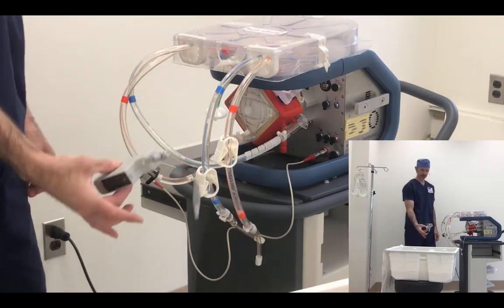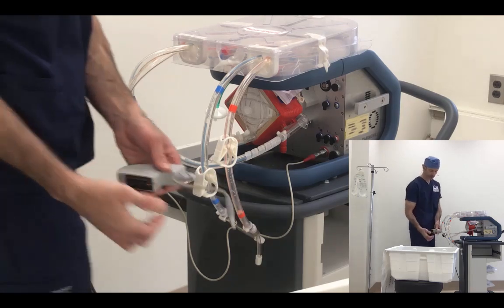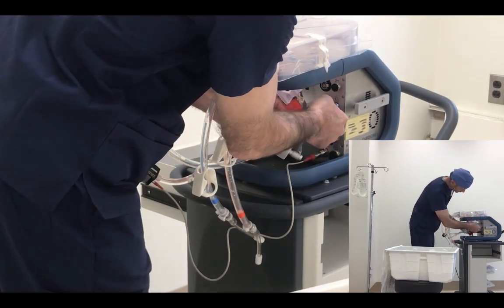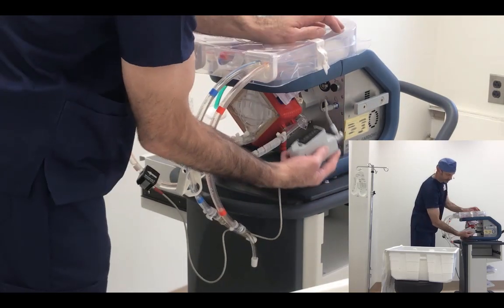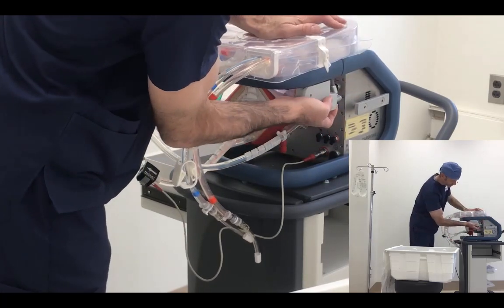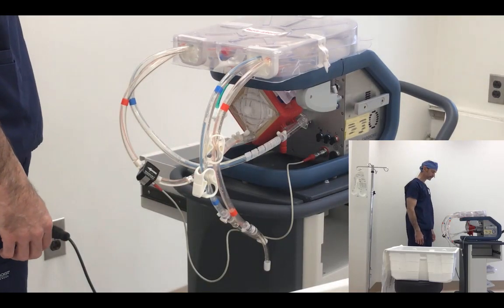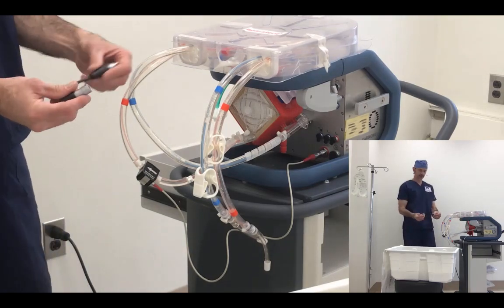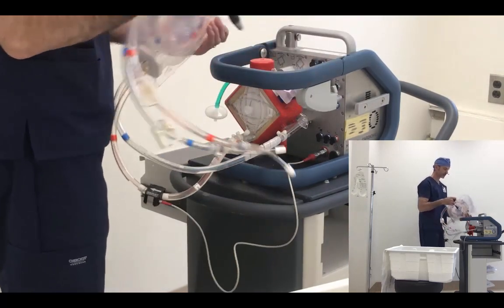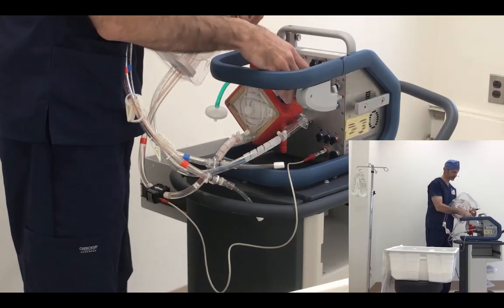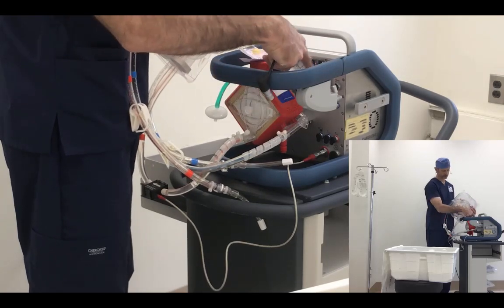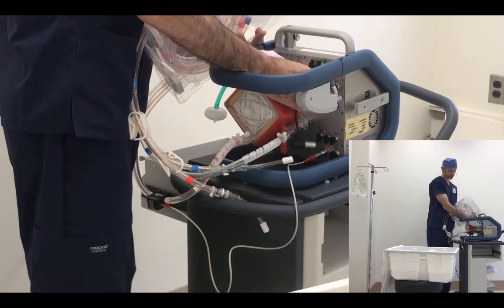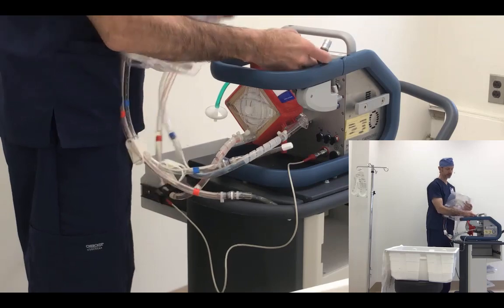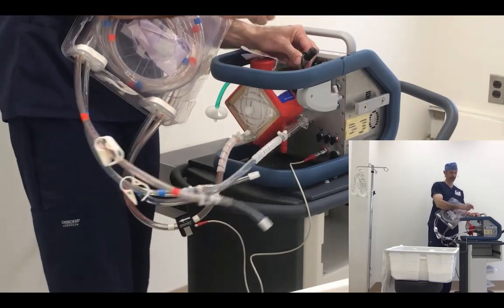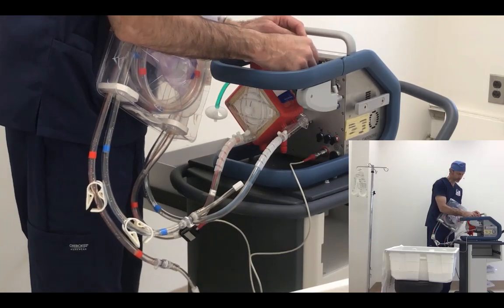We have the sat crit monitor. Find our red dot. Put it into the jack that has the icon that looks like the sat crit monitor, and connect it to the handle, to the guard up here on its mounting bracket. Next we have the data cable, necessary for the pressures and temperatures. They're going to come out of the data from the oxygenator itself. Black cable, black ring, red dot, line up the red dots, press it straight in. On the other end of this, there's a red dot here, there's a red dot there. The right angle comes up, goes back across the oxygenator, press that on. And make sure it's tight.